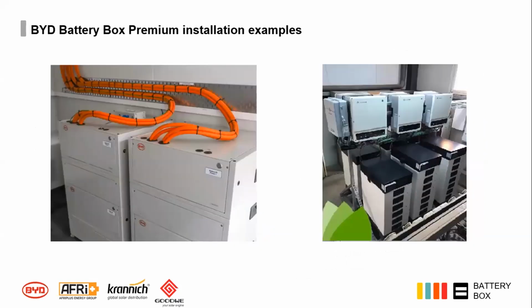Here's just some examples of the BYD Premium battery installations. On our left, we've got the LVL 15.4. That's an example of the tower design where you've got two batteries on top of each other, and that gives an amazing amount of power in a very small space. In that photo on the left is 60 kilowatt hours of battery power, and the floor space is about 1.3 meters by 700 deep. And that's quite a good energy density. And then on the top there, just behind the orange cable, you can see the BMU. And then on our right, we've got an example of how the Goodwe inverters work with the BYD high voltage batteries. And that's an application in Europe where they're using it for load shifting and time of use tariffs.